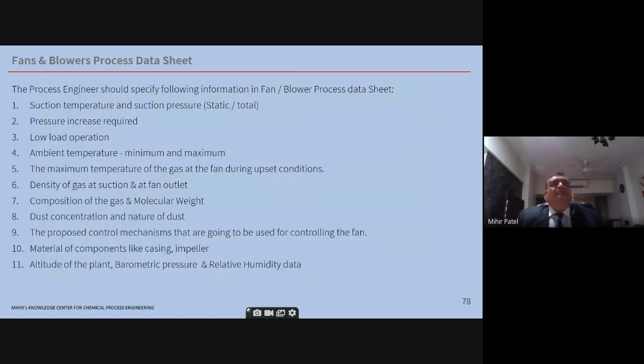Then fans and blower process data sheet. So these are the different things that a process engineer has to give for the fans and blower process data sheet. So if the blower or fan takes suction from atmosphere, the process engineer, he or she, has to specify the ambient air, meteorological data also. So ambient temperature, the barometric pressure, all this also has to be specified there. Then I will go to the next one.